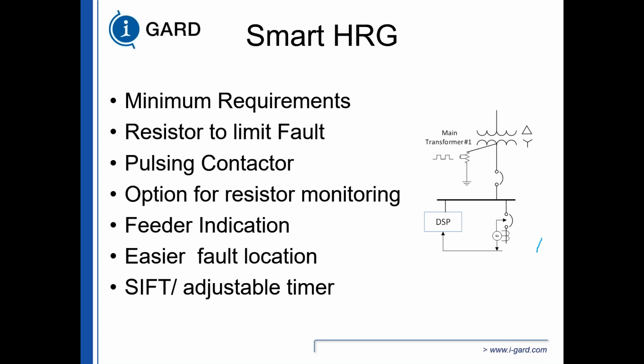In Canada, we use a lot of high resistance grounding, and we use a lot of smart high resistance grounding in hospitals because the operating room can never shut down. It has to stay up, and it doesn't matter if everything else is collapsing around it, the operating room has to stay up. So it usually has the highest priority level.